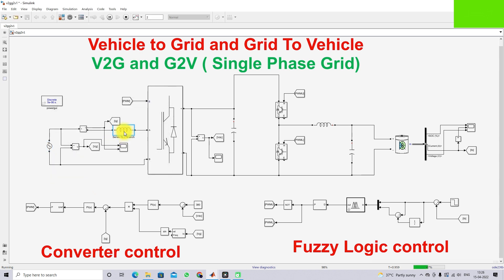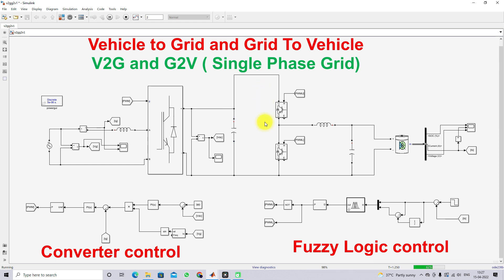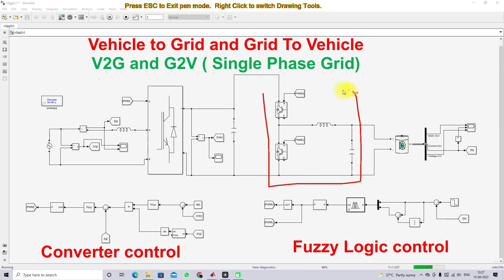There is a series inductance on the source side of 2.3 millihenry. This is a single-phase converter that can operate in both directions — it can convert AC to DC as well as DC to AC, depending upon the condition of the battery side. There is a DC link capacitor connected between this converter and the bidirectional converter.